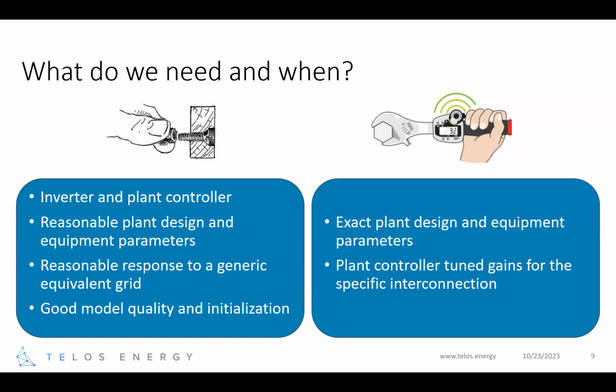I mean that the EMT model should certainly have an inverter and a plant controller, but maybe we can get away with using a generic model in some situations. Understanding that the model in the hand tightening situation, if you will, should have reasonable plant design parameters. But maybe along the process there will be a reason for something to change within the developer's line of sight to that. So having that flexibility there. We want to see these models respond reasonably to a generic equivalent grid like I showed with the test system. And we also want to ensure that the model initializes and has a good quality.